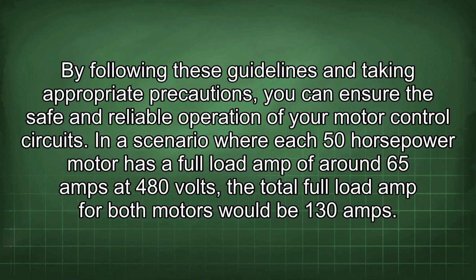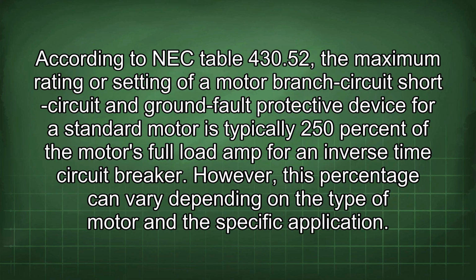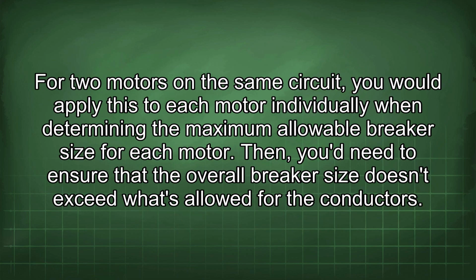circuits. In a scenario where each 50 horsepower motor has a full load amp of around 65 amps at 480 volts, the total full load amp for both motors would be 130 amps. According to NEC Table 430.52, the maximum rating or setting of a motor branch circuit short circuit and ground fault protective device for a standard motor is typically 250% of the motor's full load amp for an inverse time circuit breaker. However, this percentage can vary depending on the type of motor and the specific application. For two motors in the same circuit, you would apply this to each motor individually when determining the maximum allowable breaker size for each motor.